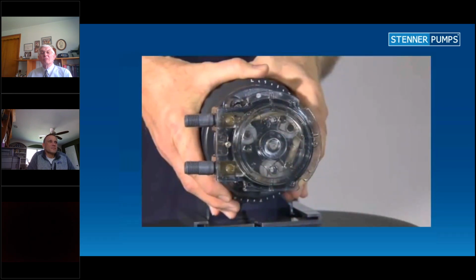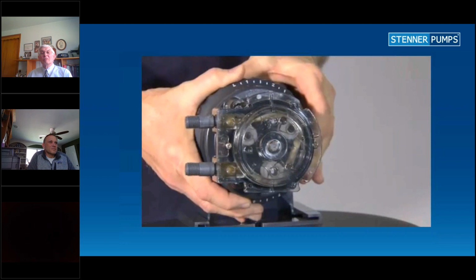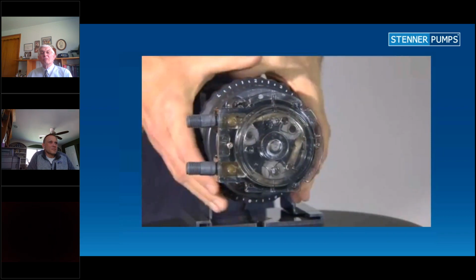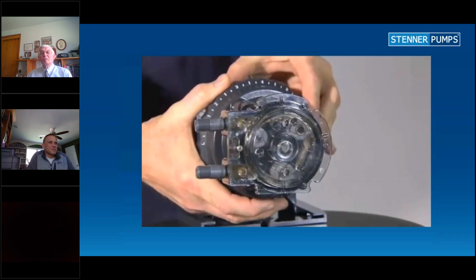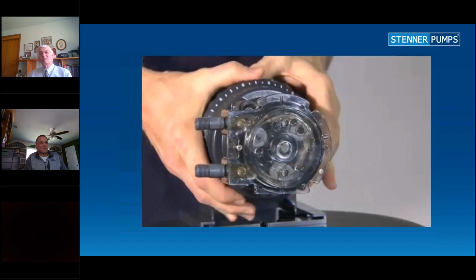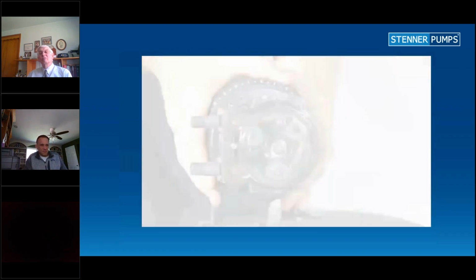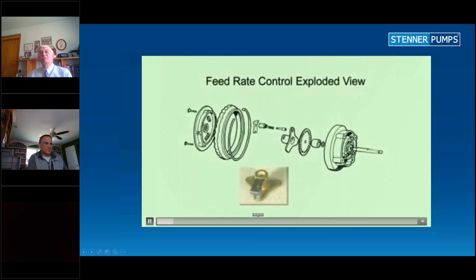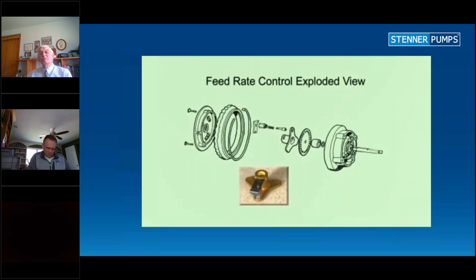The feed rate subassembly is unique to Stenner's Peristaltic metering pump in that it is a mechanical control that controls the output. The feed rate control utilizes a cam and spring-loaded lifter system to control the rotation of the roller assembly in the pump head, which adjusts the output according to the setting on the external dial ring. Inside the feed rate control is a brass spider assembly that consists of a pin and spring inside the holder attached to a lifter. When the pump is on, the spider turns.